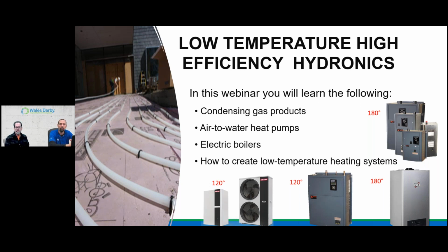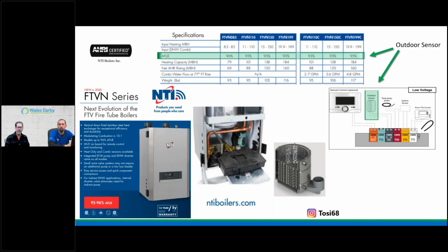But yeah, the truth about condensing gas and why it is engineered to be so efficient has to change the way we approach the install. All right, so we'll discuss a good bit of those. Just to knock down what a condensing boiler looks like: it's manufactured to be in an environment where flue products that are saturated collapse back to a liquid, that condensation that flows across the heat exchanger. Then we're left with the good stuff, that higher efficiency, that state where we're condensing. Now we're playing up in the 90, 92, 93% maybe.